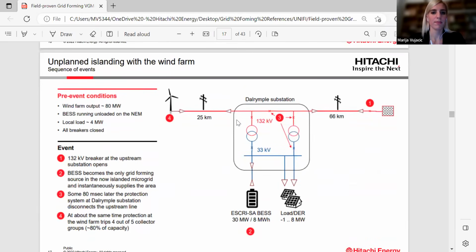The second event, which was also demonstrated during the commissioning time, was the case when the wind farm was connected. So please note the size of the wind farm. The output of the wind farm was 80 megawatt. Again, BESS was running unloaded, and at this moment the local loads were around 4 megawatt. At the first moment, the 132 kV breaker at the upstream substation opened. BESS became the only grid forming source in the islanded microgrid.